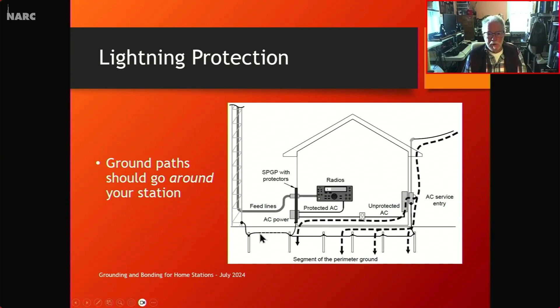Lightning current is no different than any other type of electrical current, and it will divide according to the resistance that it sees in each branch. So give it lots of branches to go outside and dissipate into the earth and not have to flow through your equipment on the way to a ground.